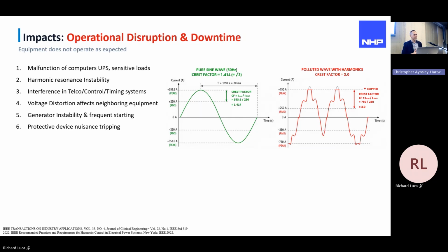We've got generator instability and frequent starting. The recent one: a phase failure relay, constantly calling the generator due to a phase imbalance. Protection devices nuisance tripping. Now I'll put these two waveforms in here. So the green one, green is good usually. If anyone knows the crest factor, it's the peak to the RMS figure. And in a pure 50 hertz wave, the crest factor equals 1.4, thereabouts. In the red, if we've got a highly polluted waveform propagating throughout your network, you could have a crest factor of 3 or greater, which means you're going to have a really peaky waveform.